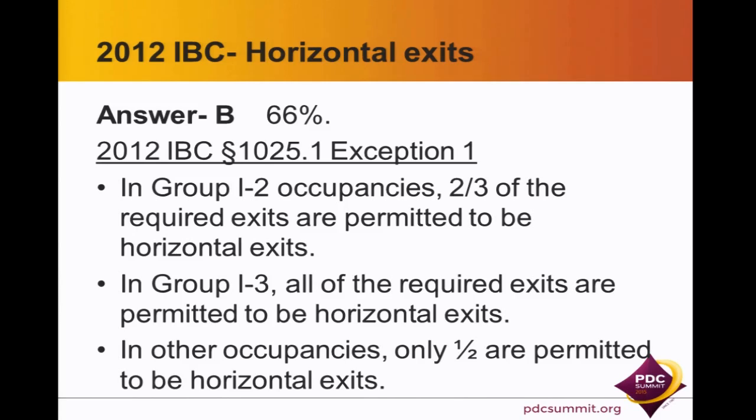Yes. The biggest violation we see is somebody has a problem on a floor, they say, oh, we'll put a horizontal exit up, and they say, oh, but the floor is 2 hours, which is fine, but then if the barrier doesn't go all the way to the ground, all your other exits serving that area have to discharge to the outside. And that is commonly overlooked, or we see it commonly overlooked. I'm sure nobody in this room would do that, but we have seen a number of firms do that.